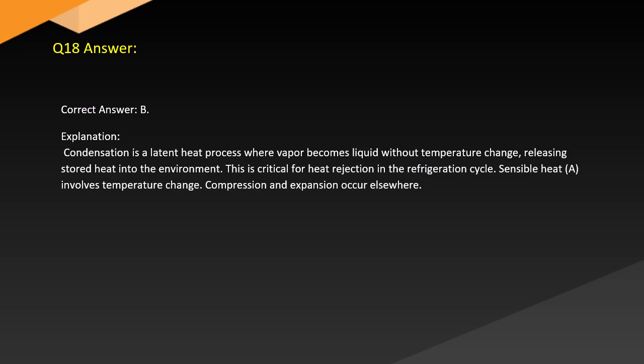Answer. Correct answer: B. Explanation. Condensation is a latent heat process where vapor becomes liquid without temperature change, releasing stored heat into the environment. This is critical for heat rejection in the refrigeration cycle. Sensible heat involves temperature change. Compression and expansion occur elsewhere.